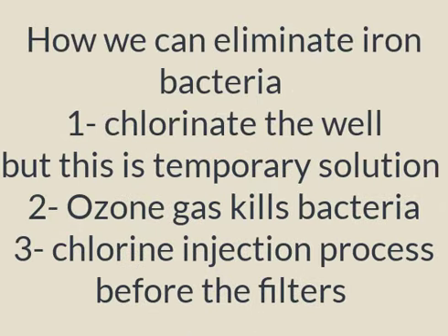Now, how can you eliminate iron bacteria? You have the option to chlorinate the well, but this is a temporary solution, and you can go for ozone gas, which oxidizes the iron and the sulfur in the water, and this is going to kill the bacteria. And you can go for a chlorine injection process before the filters.